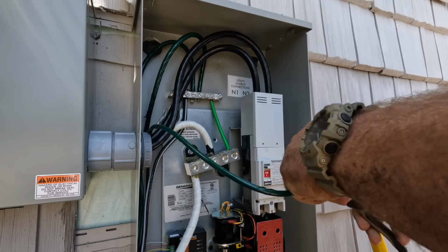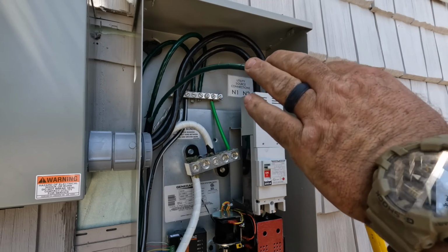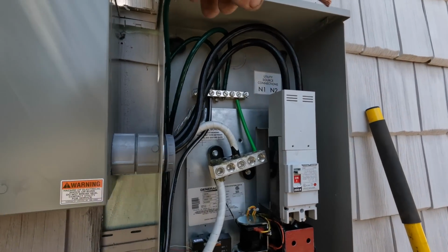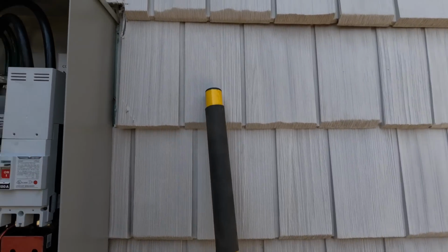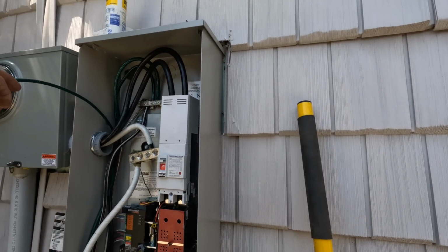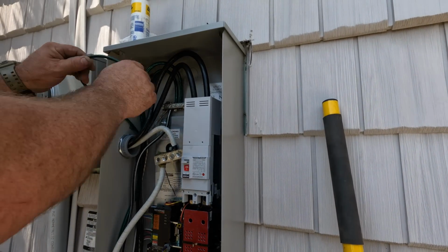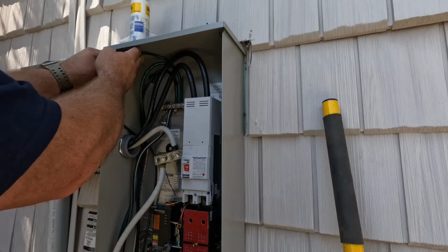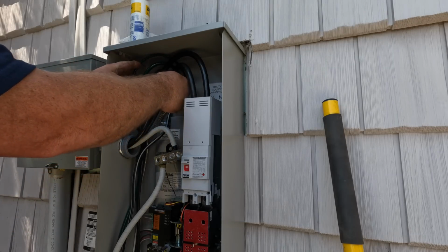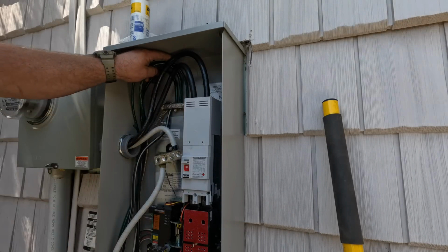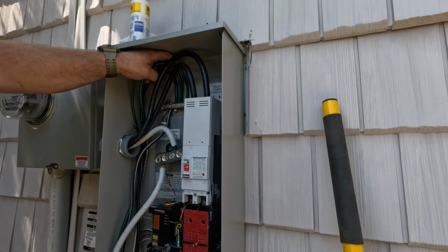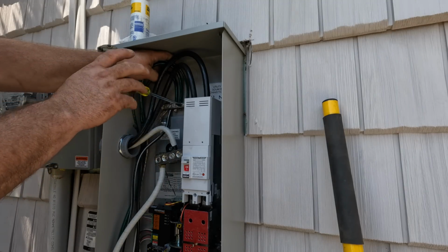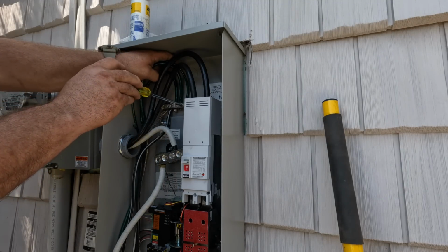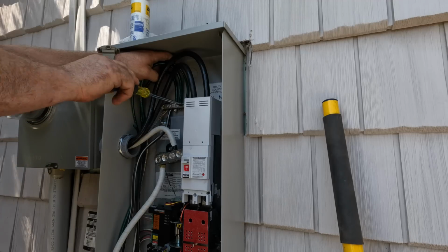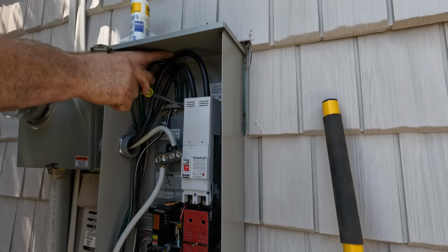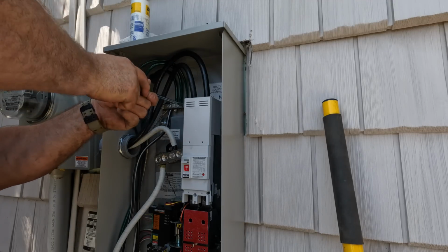Everything inside this transfer switch right now is live. Obviously, you've got to use caution when you're doing that, especially when you're holding onto a grounding connector connected to the ground. If you come in contact with the live conductor while you're holding onto that ground, you'll have some current going through you for sure. You'll definitely feel it, and you could die very easily.